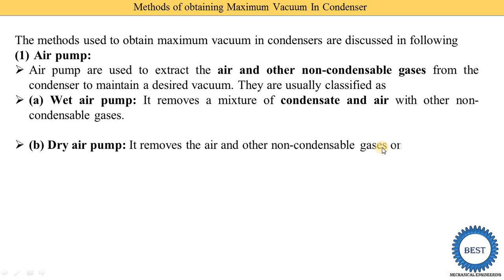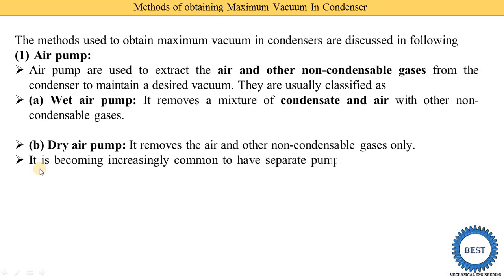The second type is the dry air pump. The dry air pump only removes the air and other non-condensable gases — no condensate is removed. It is becoming increasingly common to have separate pumps for extracting the air and the water from the condensate. A separate pump is used to remove the air, called the air extraction pump, and a separate pump to remove the condensate, called the condensate extraction pump.